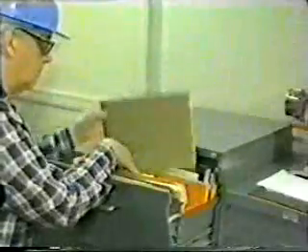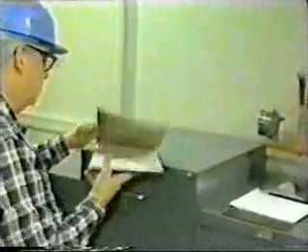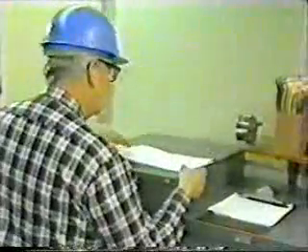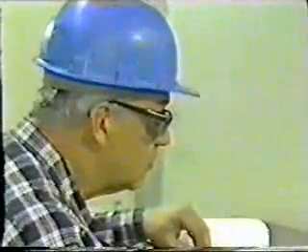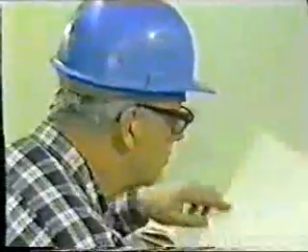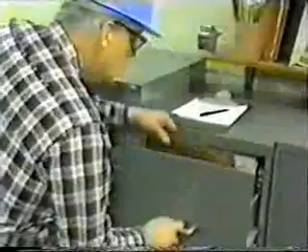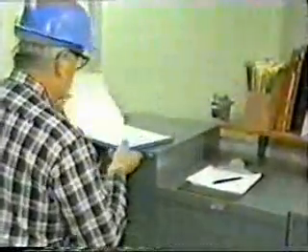To find a probable cause, Gene will concentrate on investigating these 3 areas. First, he'll go through plant records. He takes a look at the operating log. It shows notations of when excessive gland leakage started. There is no other mention of the problem. The maintenance log, however, contains some information that sheds quite a bit of light on the problem.